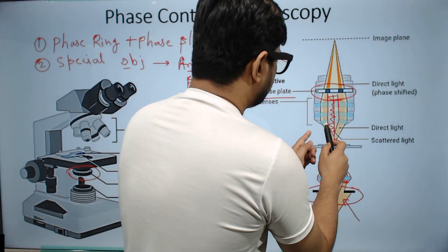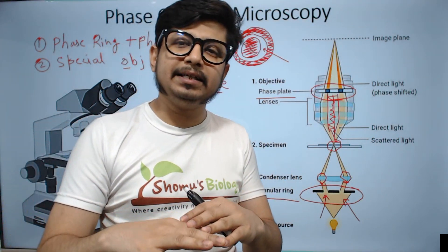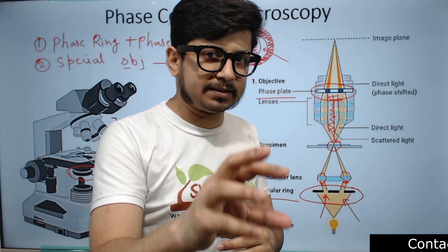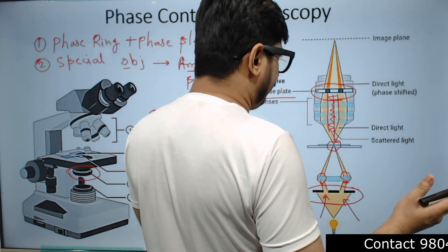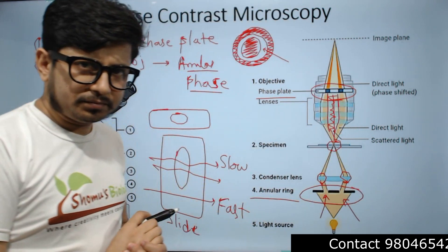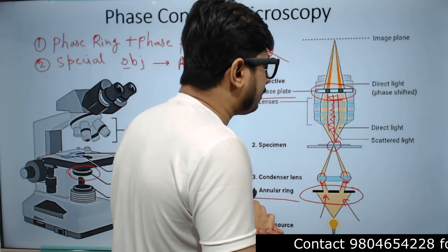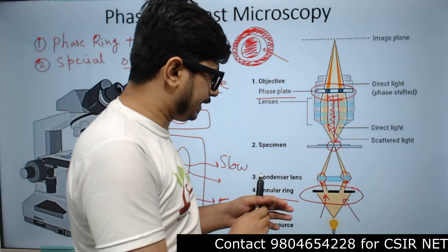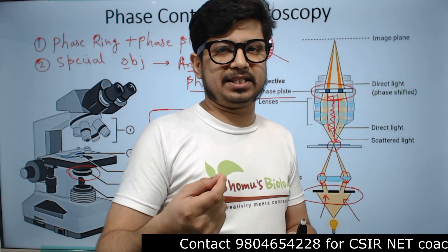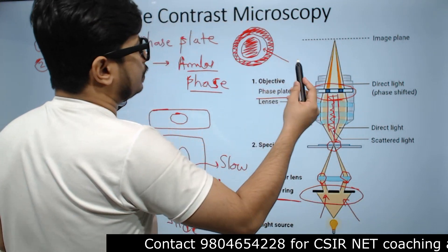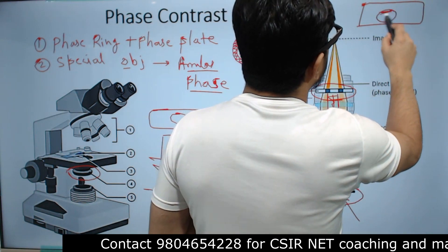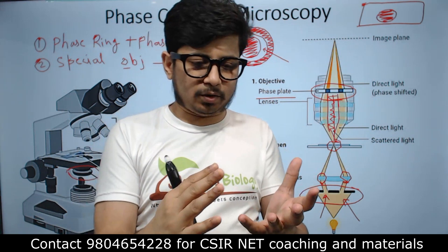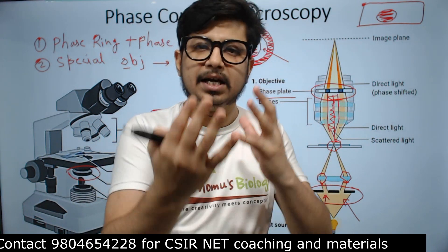The light passing through the periphery via the objective comes from the background with no scattering, while the light coming from the center of the specimen is scattered light. So there are two kinds of light: direct light at the periphery and scattered light from the center. As I mentioned, the light wave moves slowly through the specimen and faster through the background, causing a phase shift. Using the annular ring alone we can create some contrast — a dark background and a lighter specimen — but it provides only a little more contrast than the existing specimen.